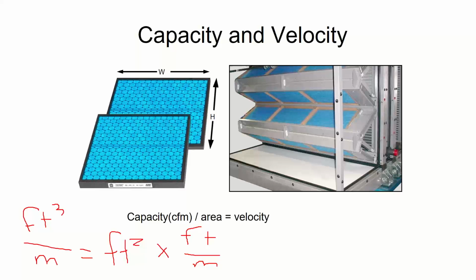So we put this V-bank in to get more surface area, because if I can increase the area, that will decrease the velocity, right? Because the CFM has to stay the same. I want the slow velocity because it's going to be easier for me to catch stuff on the filter. If I have high velocity, I'll have high velocity pressure, and I'll be able to shove the dirt through the small holes. If I have low velocity, it'll get caught on the filter and not get as easily shoved through the holes. So I put in this V-bank pattern, because I'd like to have it be really tall.